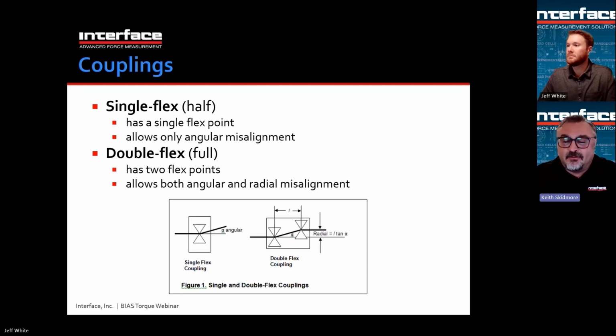And that allows for both angular and radial misalignment, as you can see by moving the two angular displacement points away from each other by the distance L. You can then allow for a radial displacement equal to L times the tangent of alpha, and alpha is the allowable angle of displacement. And typically a coupling will be rated for around 1 degree of displacement.